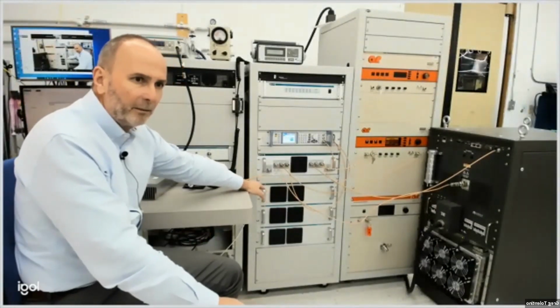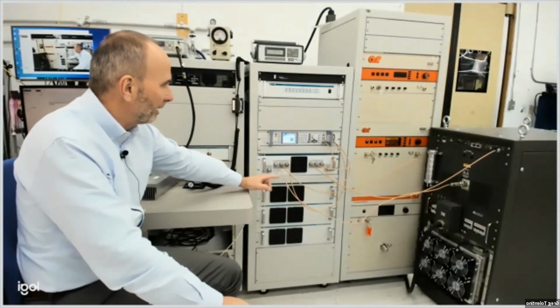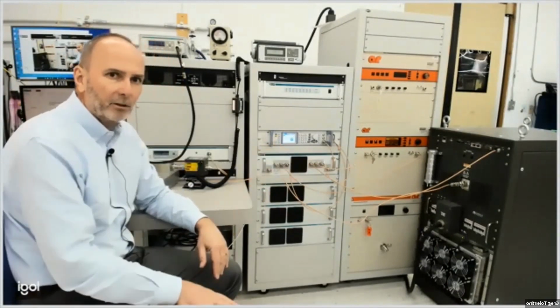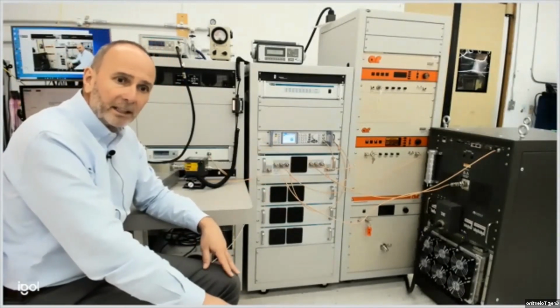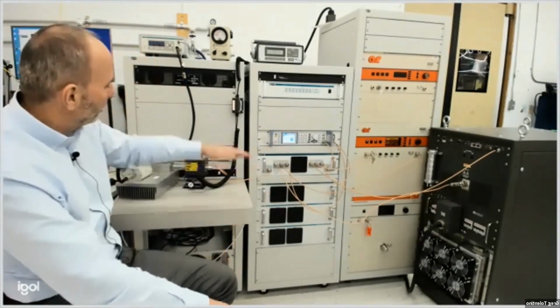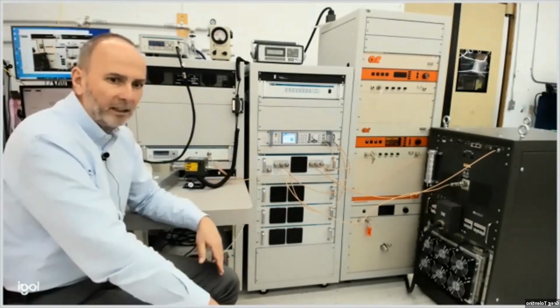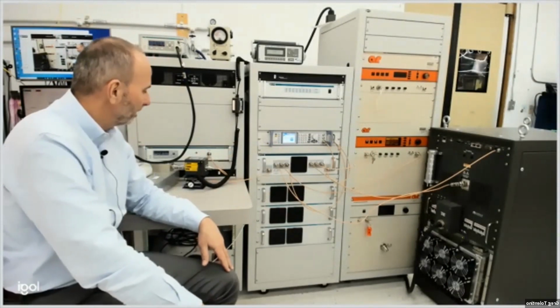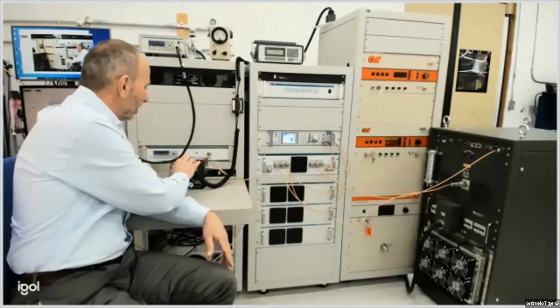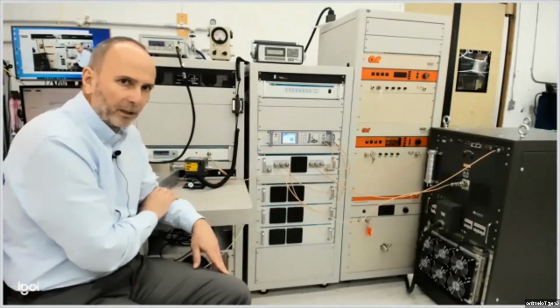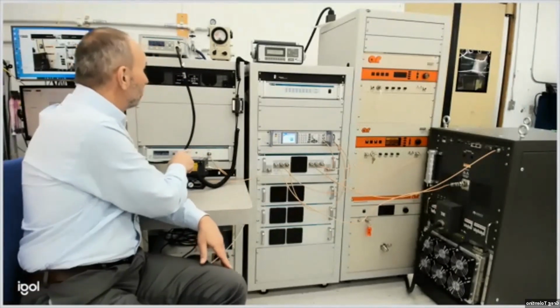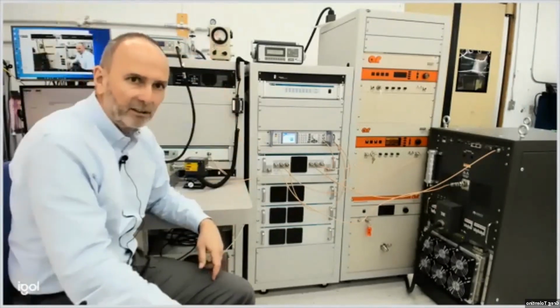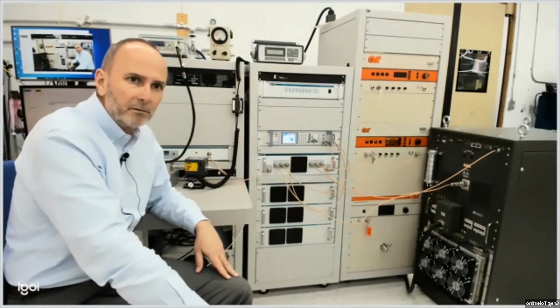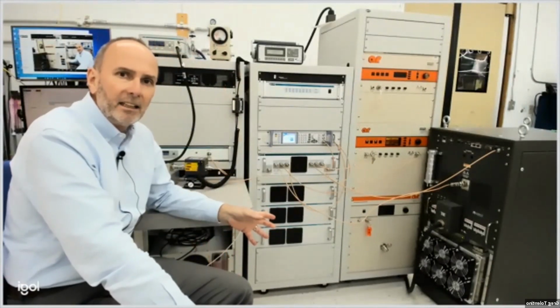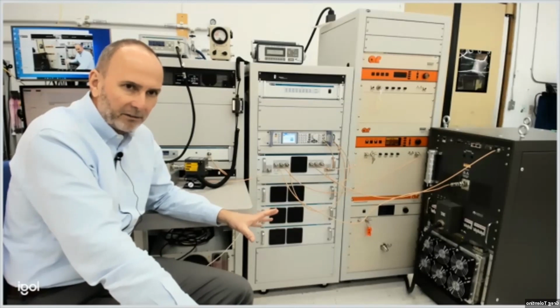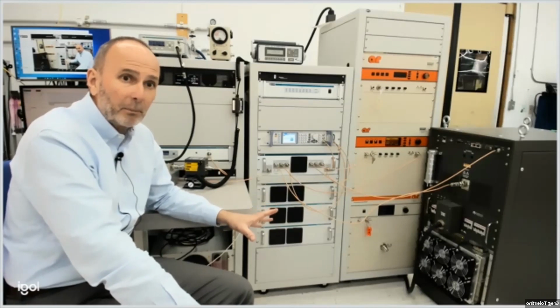So with 30 dB of cut on the harmonics, and amplifiers that are all being operated in the range where they will produce less than 20 dB of harmonics, we're putting less than 50 dBc of harmonic content into the sensor. That is appropriate because both of these types of sensors are diode detectors, so effectively peak voltage indicators, and any harmonics could distort the wave shape and give a very incorrect power reading.